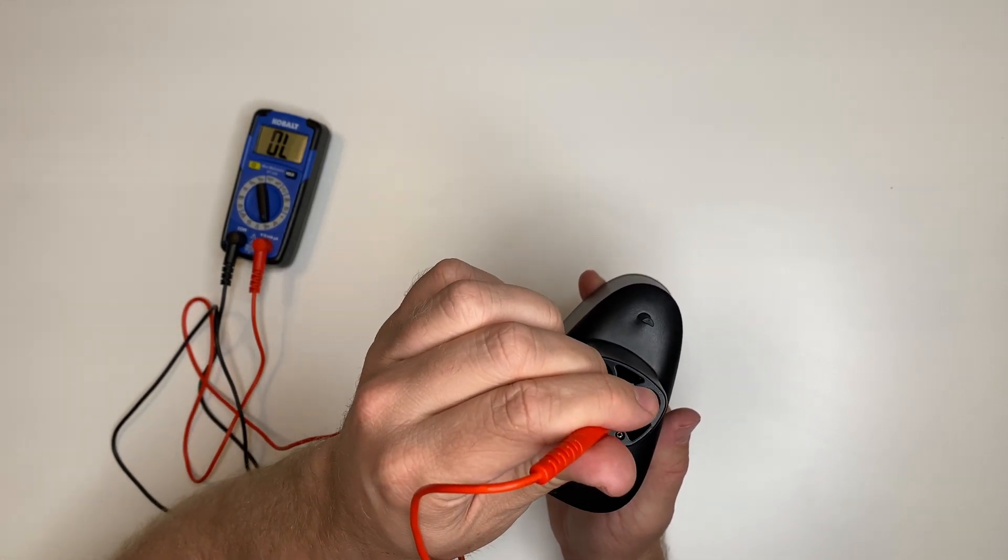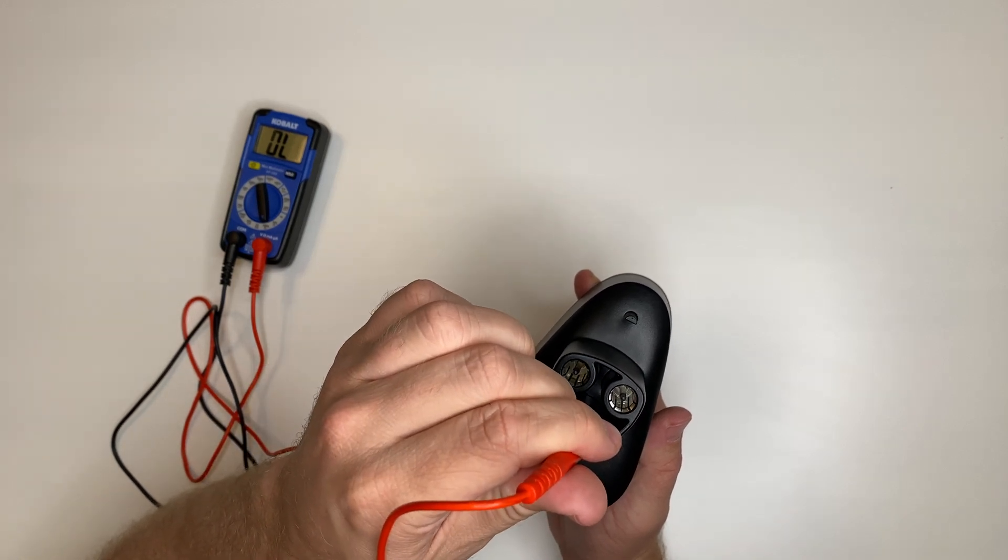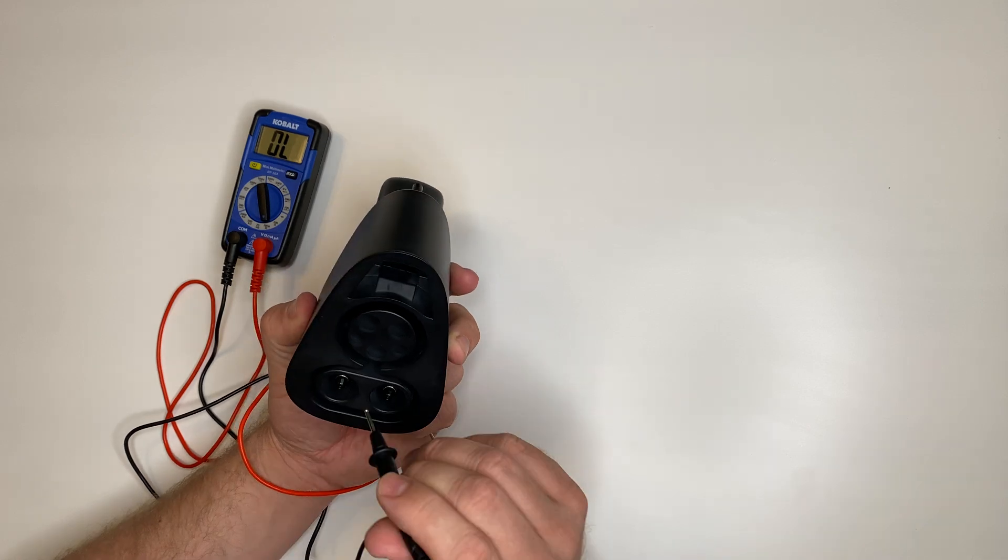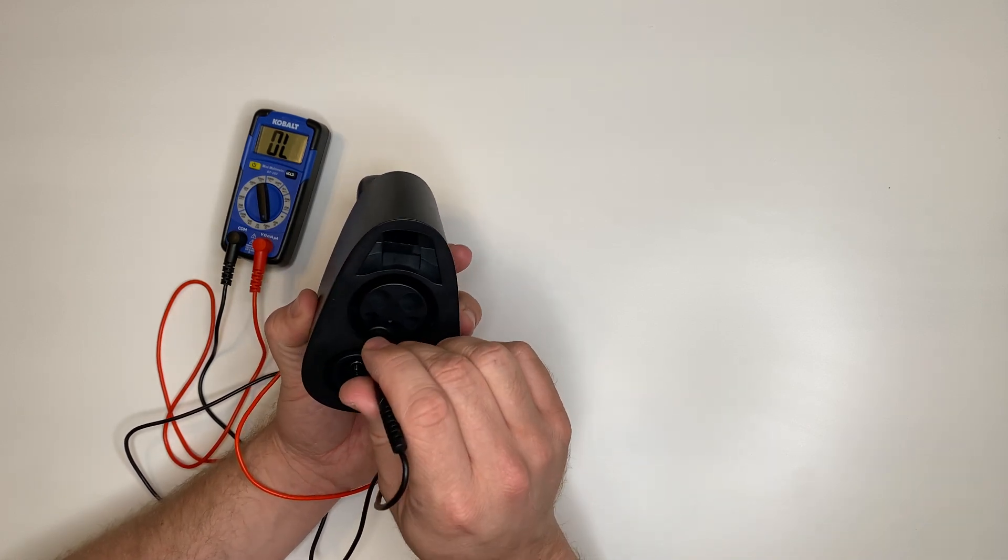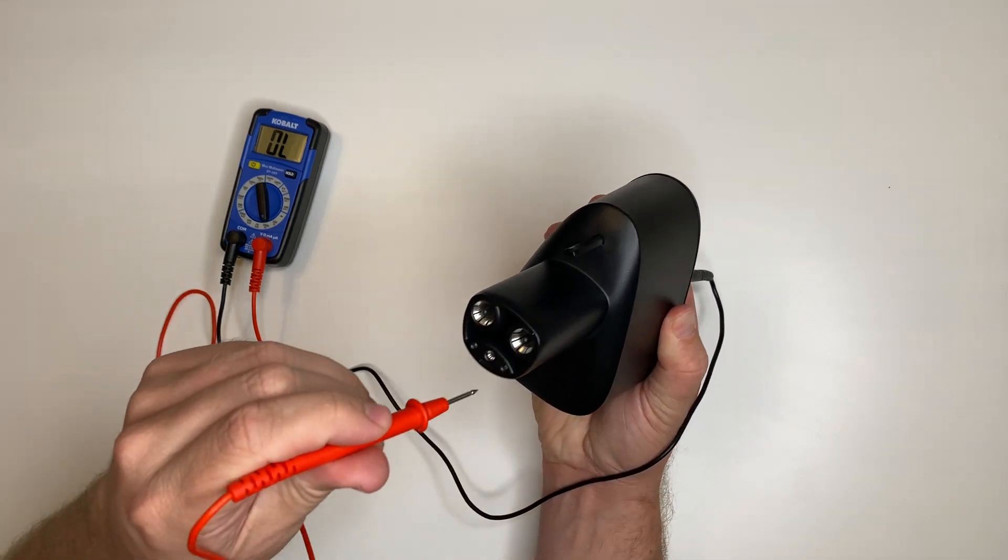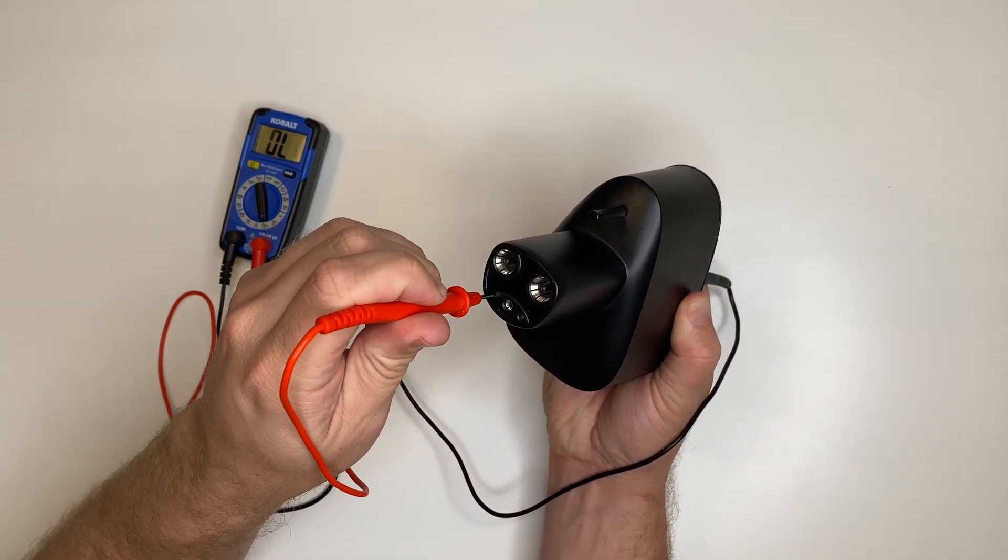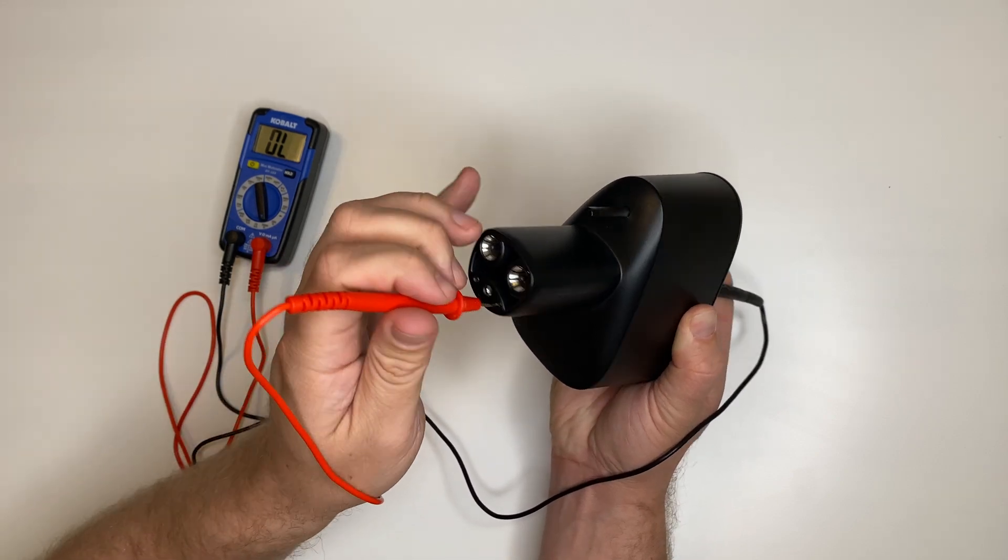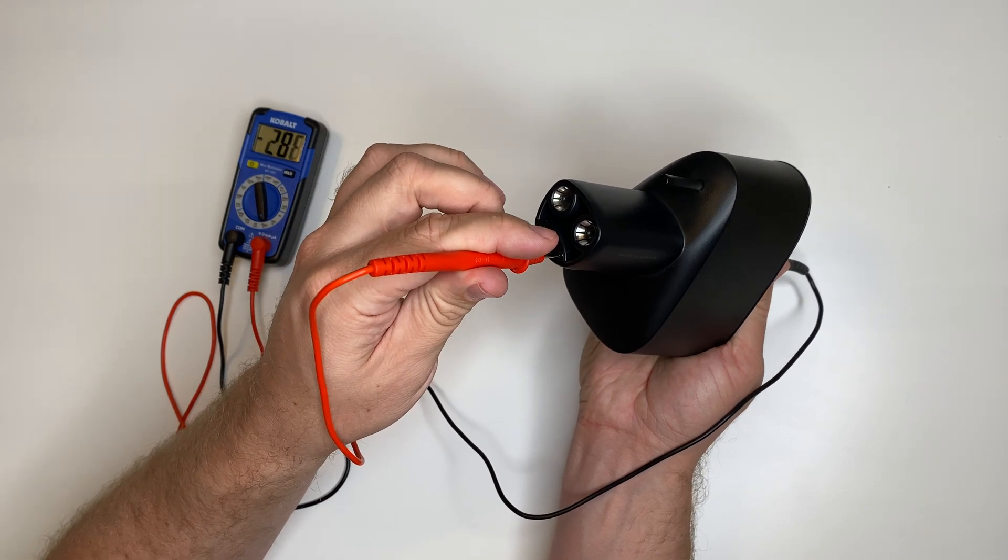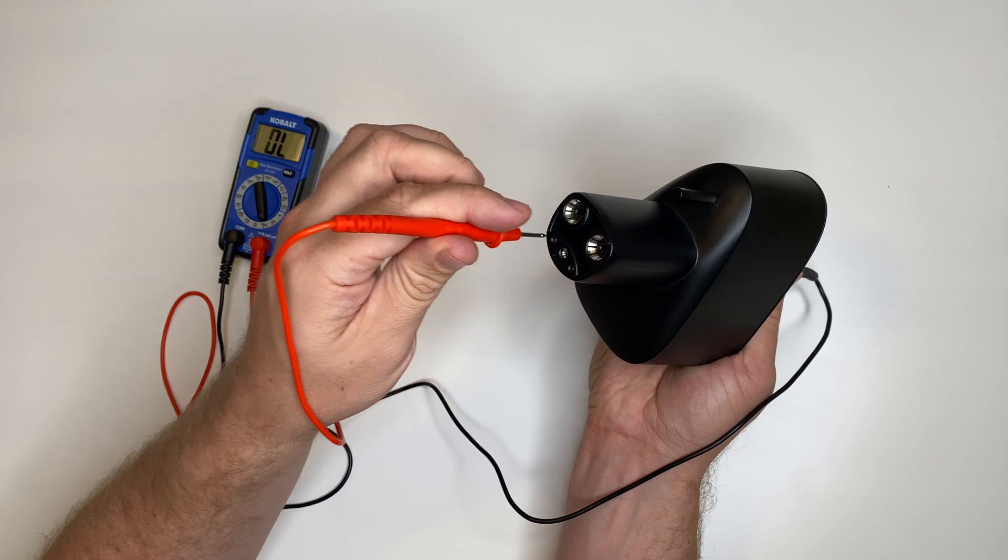The same applies for contact 4 over here, which is the control pilot. On the corresponding side, you see zero ohms, and any of the other pins show no connection.